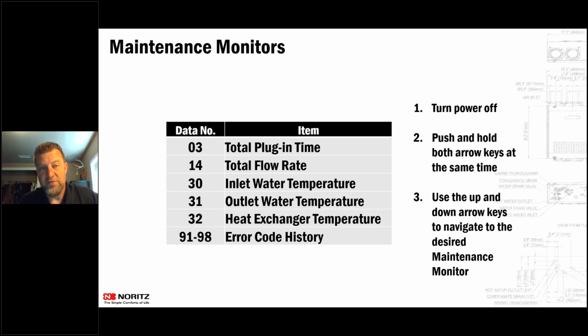With tankless, we have a throttling valve leaving the unit, and you'll lose pressure over the heat exchangers. With our units, it might be 5 to 6 pounds. With some manufacturers, depending on the flow rate, it could be 15, 20, 25 pounds over that heat exchanger. But that small differential with ours, that 5 pounds, if you have a bad cartridge, is going to let that pressure push through and let cold bleed into the hot side, so you're only going to get lukewarm water. So if you ever run into that, always check that maintenance monitor. It'll show you that 120 degrees is leaving the unit and that it is something inside the house causing that cross connection versus something wrong with the actual unit.